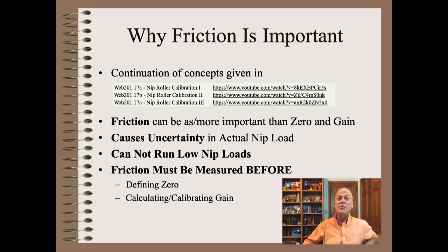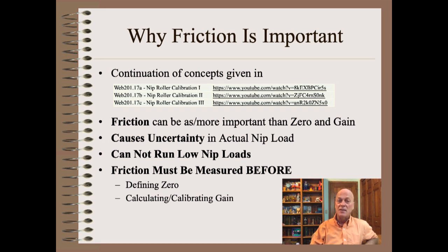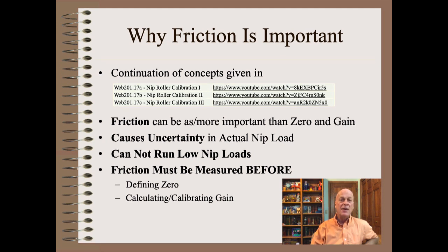In the last three clips, which I urge you to study first, we showed you how to calibrate zero and gain of systems with friction. We showed that friction causes uncertainty in actual nip load on the product. We also showed how friction prevents you from running low nip loads, else you risk bouncing off the product and possibly causing a crash. For these reasons, friction must be measured before you do anything else with the control system.